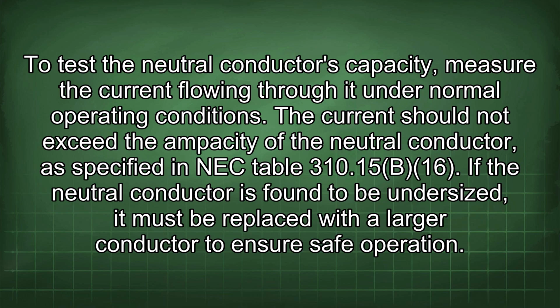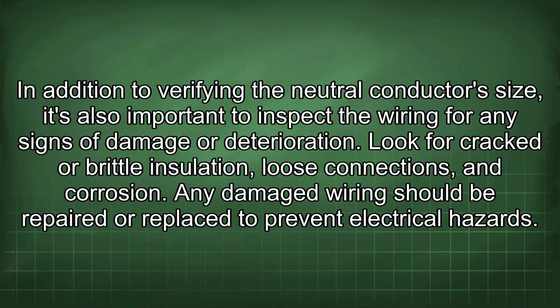The current should not exceed the ampacity of the neutral conductor, as specified in NEC Table 310.15(B)(16). If the neutral conductor is found to be undersized, it must be replaced with a larger conductor to ensure safe operation. In addition to verifying the neutral conductor's size, it's also important to inspect the wiring for any signs of damage or deterioration. Look for cracked or brittle insulation, loose connections, and corrosion. Any damaged wiring should be repaired or replaced to prevent electrical hazards.